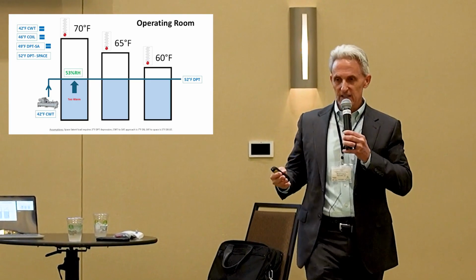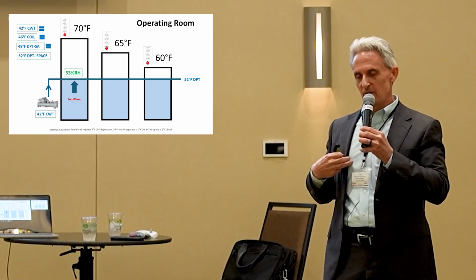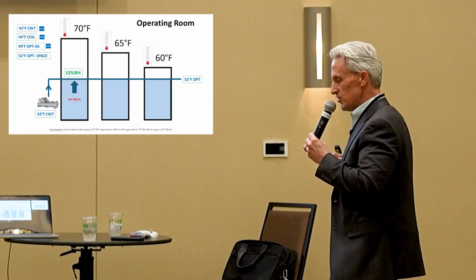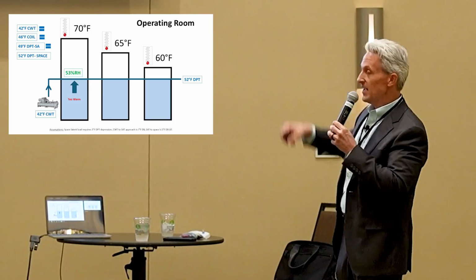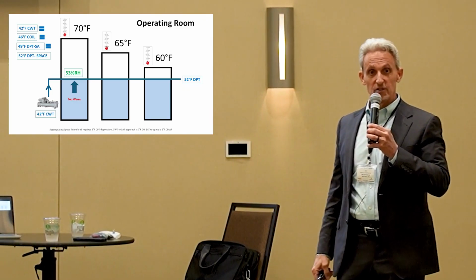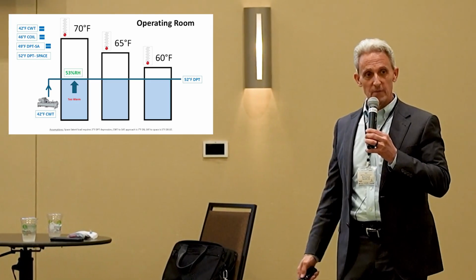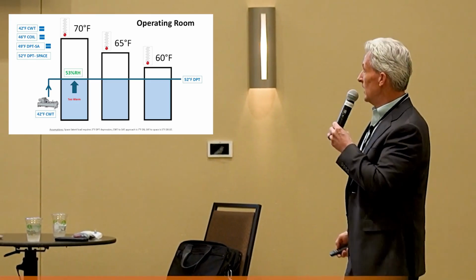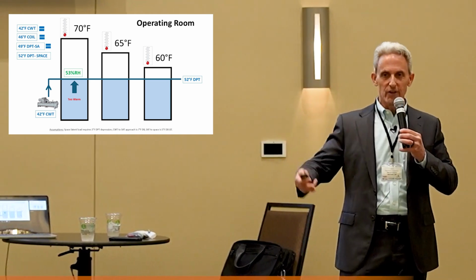Now, that relative humidity isn't terrible. That's what I might like in my house, you know. For me, up here, walking around in a suit jacket, 53% probably isn't too bad. But I'm going to tell you right now, 70 degrees is sure too warm for an ortho surgeon, right? I mean, just the temperature alone, way too warm. They need it colder.